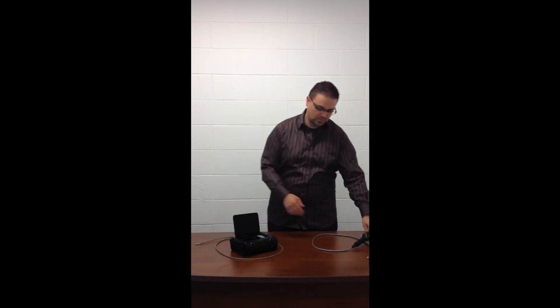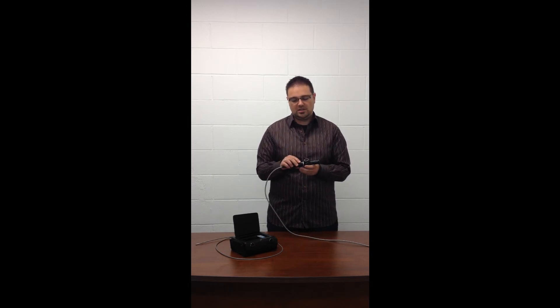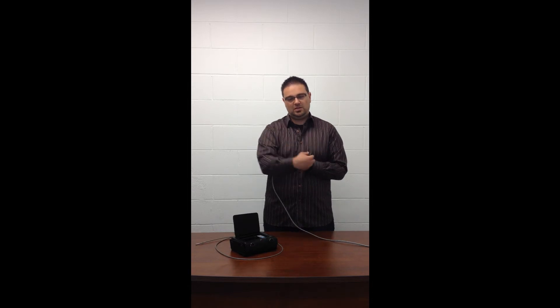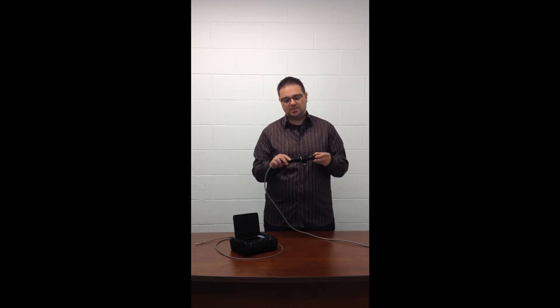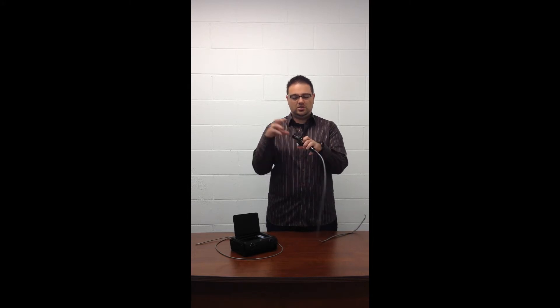For a fiber scope, obviously because there's an eyepiece on the end of the unit, you have to look through it to do your inspections. If you want to capture video or capture images to document for people, you're going to need to attach a video camera to the eyepiece. So instead of just holding this unit and doing your inspections, you're going to have an eyepiece coupler along with the camera unit, and then that's going to connect to your TV.